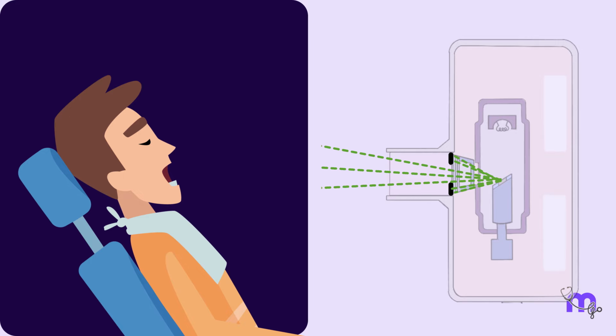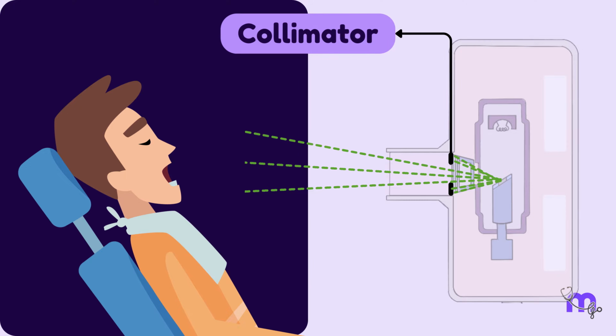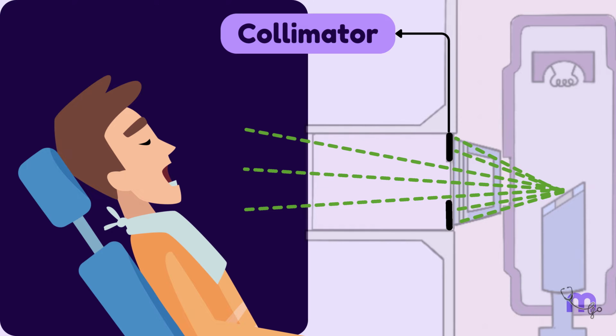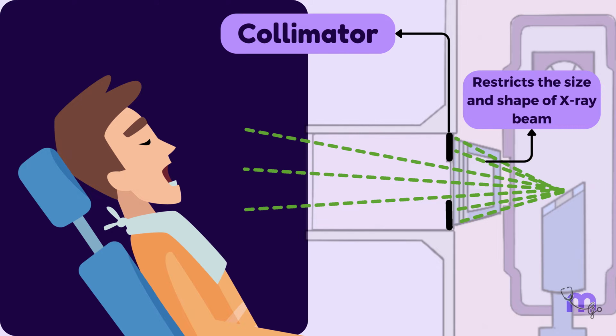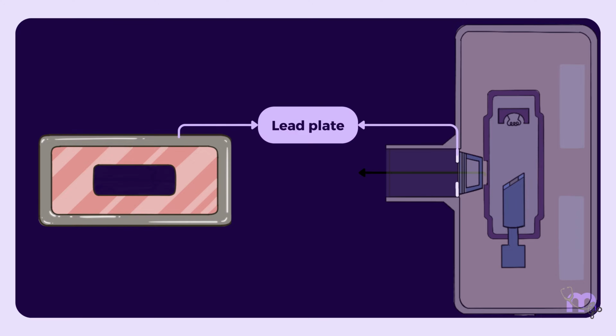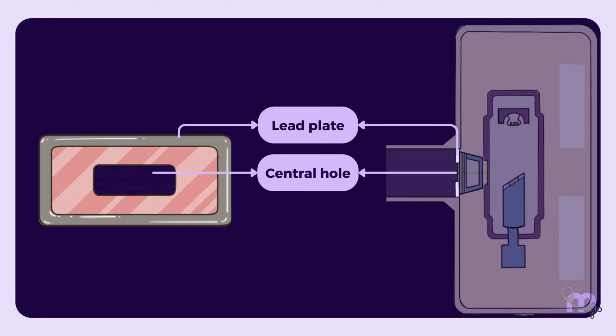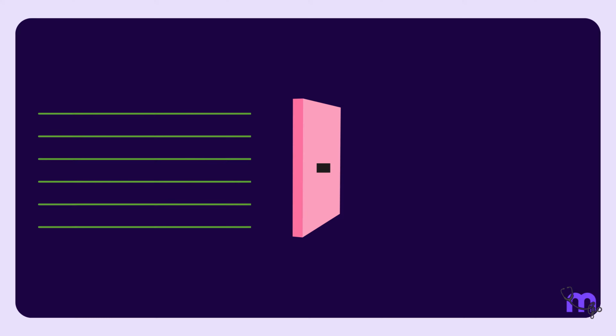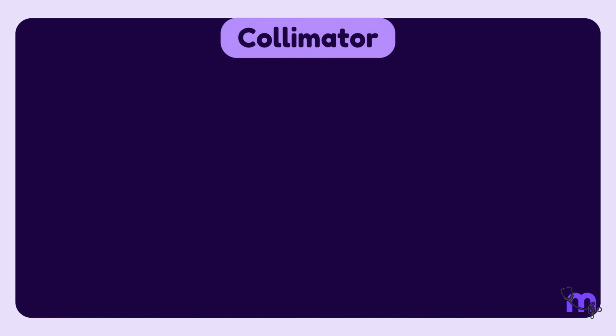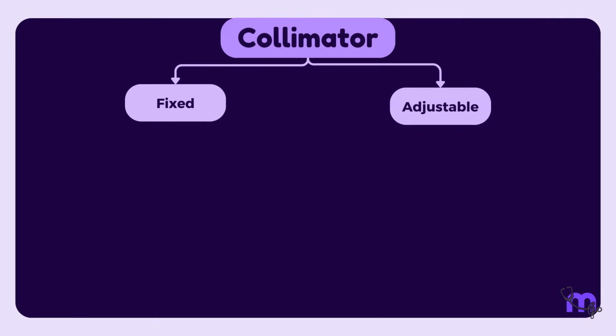Alongside filters, another safety feature called a collimator helps protect patients from unnecessary radiation. This component restricts the size and shape of the X-ray beam, minimizing patient exposure. It is made up of a lead plate with a central hole that fits directly over the opening of the metal housing where the X-ray exits. Imagine it like a blindfold with a central hole, only allowing the light to pass through a specific area. Collimators can be fixed or adjustable.